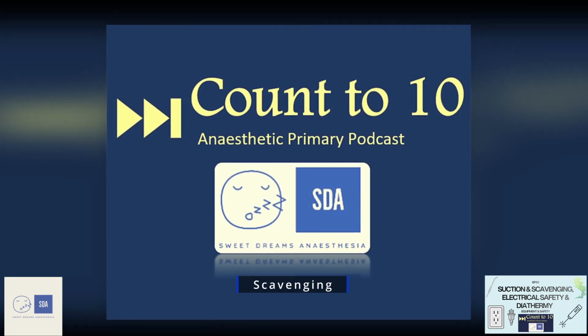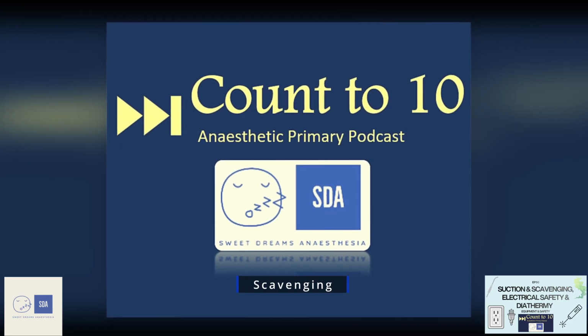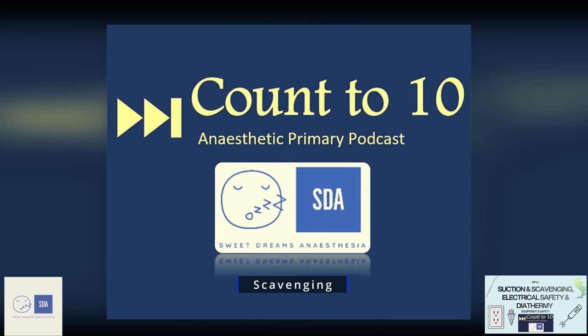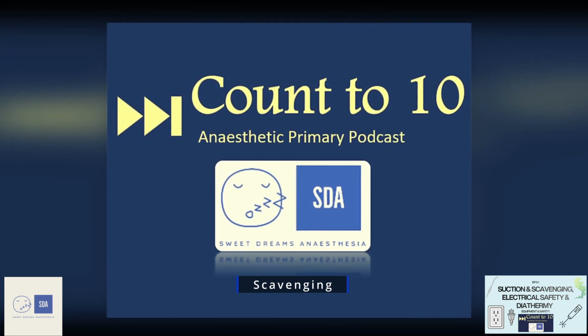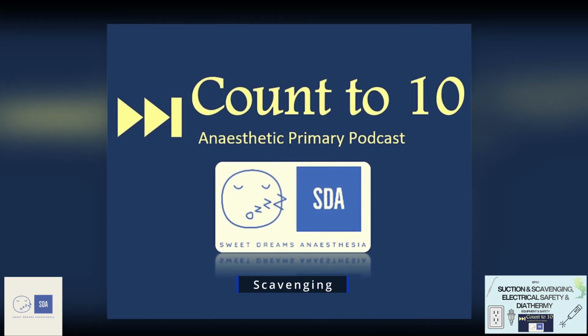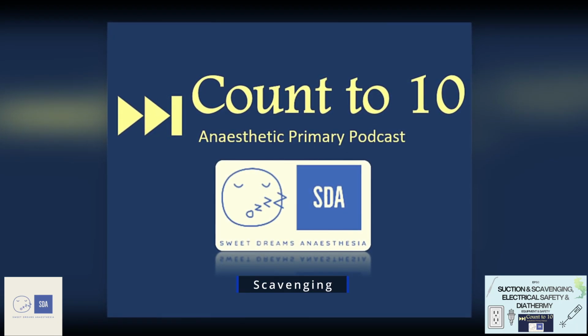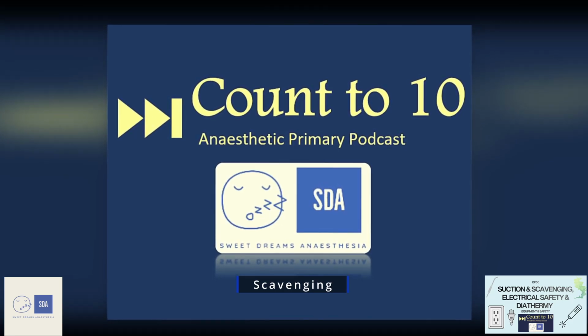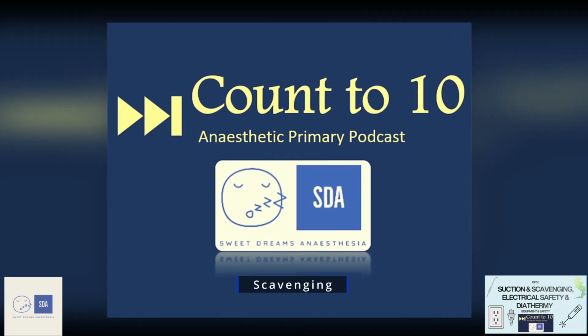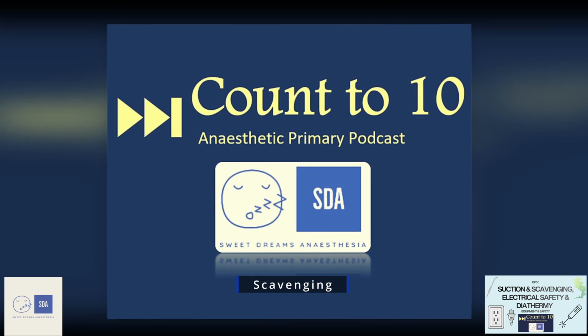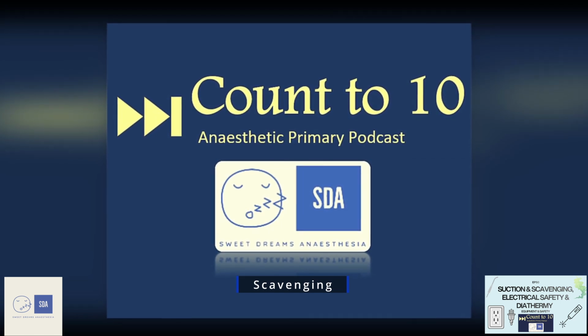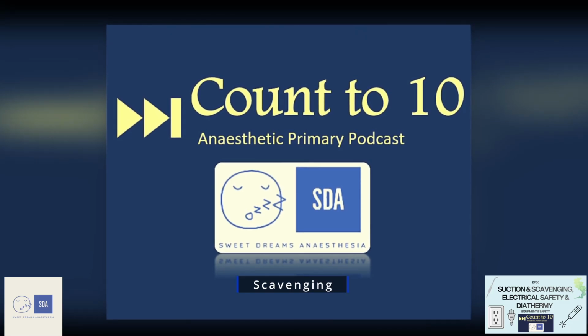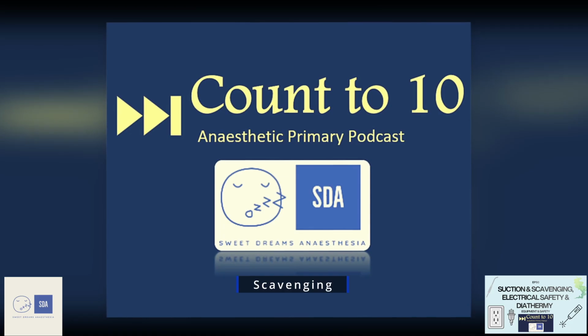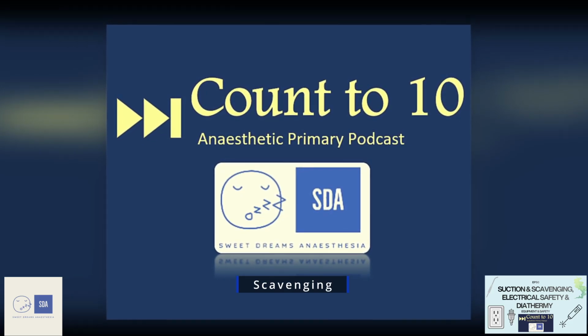If you have an active system, essentially here, this is working the same way as a vacuum works for a suction. A pump is used to generate negative pressure, which can achieve peak flow rates up to 130 litres a minute. These flow rates are higher than the average flow rates of waste gases, but they don't produce high pressures. The reason why you don't get high pressures is because these active systems are open systems, which means they have small apertures which entrain air to decrease the pressure buildup within the scavenging / receiving interface. And by having this interface exposed to air, aka being open, the negative pressure buildup becomes negligible, and therefore the risk to the patient itself of getting barotrauma or experiencing high either positive or negative pressure is very low. So therefore it's a very safe system to have, but it's a system that requires electricity and power and therefore costs money.